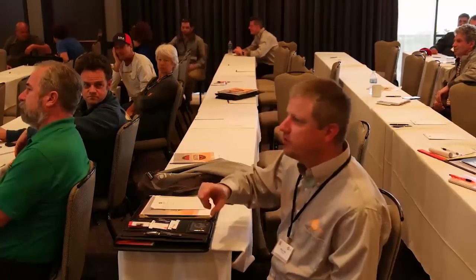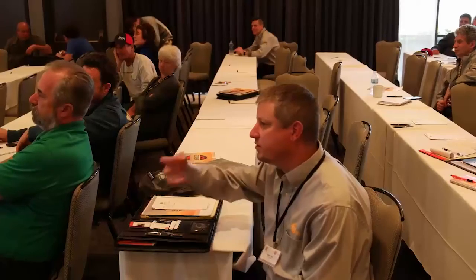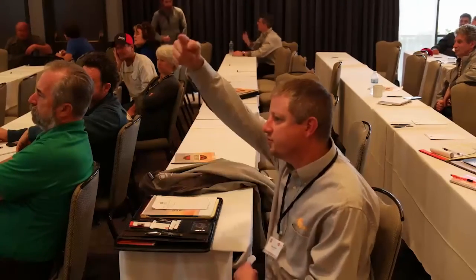On the center fed panel exemption, is there a requirement to still locate the breaker as far away from that center fed tap as possible, or can that be anywhere in there? It says it can be at either end, but not both ends. And do you want to put the bigger breakers in between if possible? You had the choice on which one to go to? The more heavily loaded side of the panel is the better place to put the PV. In general, that is the topmost space.